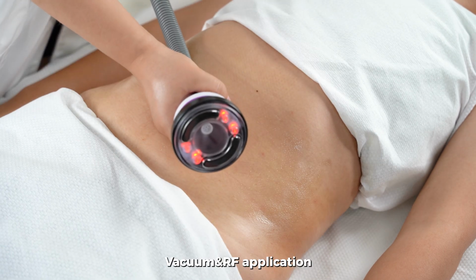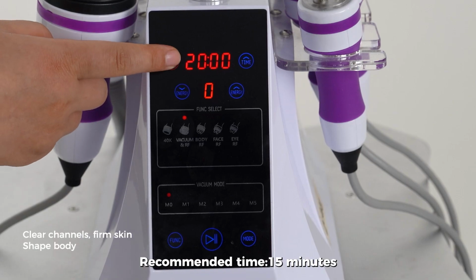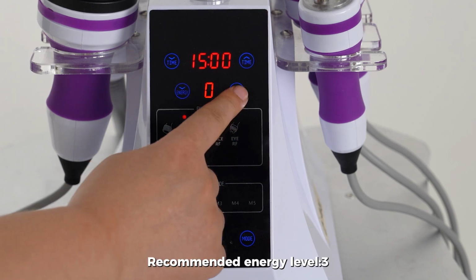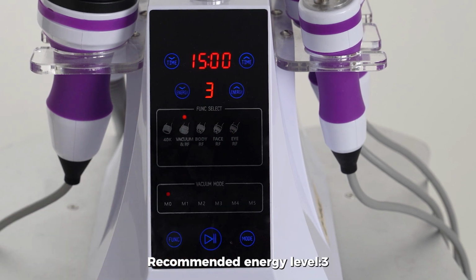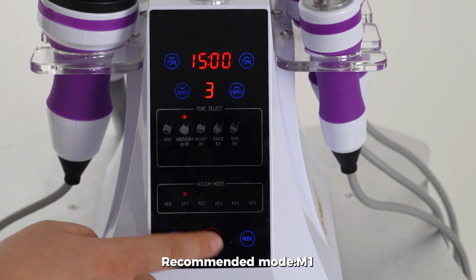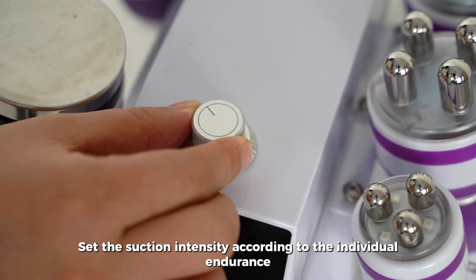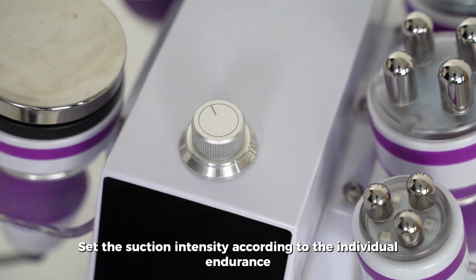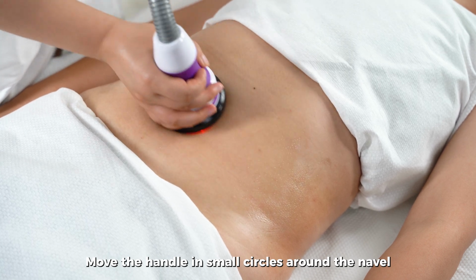Vacuum and RF application. Recommended time, 15 minutes. Recommended energy level, 3. Recommended mode, M1. Set the suction intensity according to the individual endurance. Move the handle in small circles around the navel.